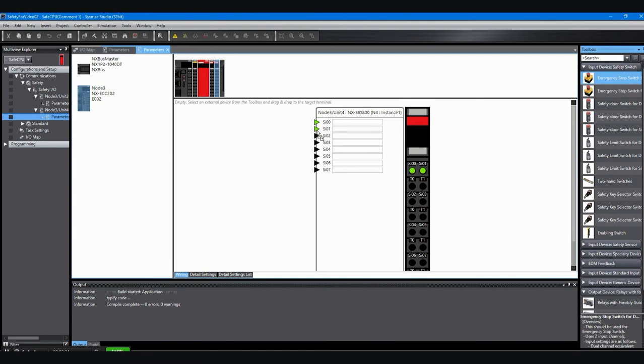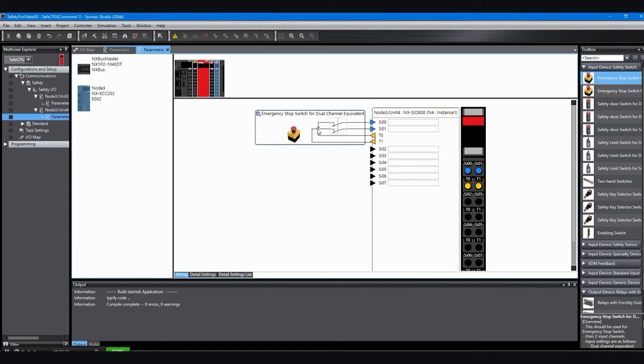But if I try to drag it to the second input point, it still uses the first and second input points. So when you have dual channel devices, they have to be put on the even numbered inputs or they have to start with the even numbered inputs. So once again, I see a simple wiring diagram here and I can add a comment. I only need to comment the first input point.